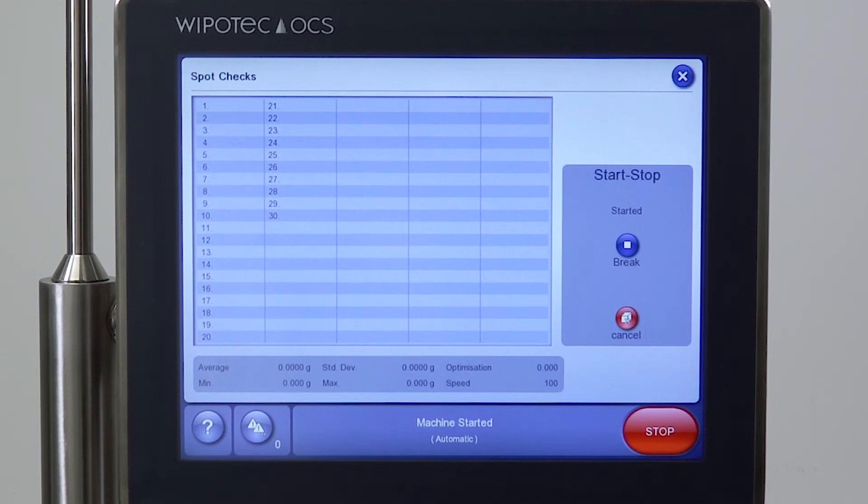Once the checkweigher is started, we place the weigh stone of 50 grams onto the weighing conveyor and we're starting now to initiate 30 times the weight reading of that precise weigh stone of 50 grams.